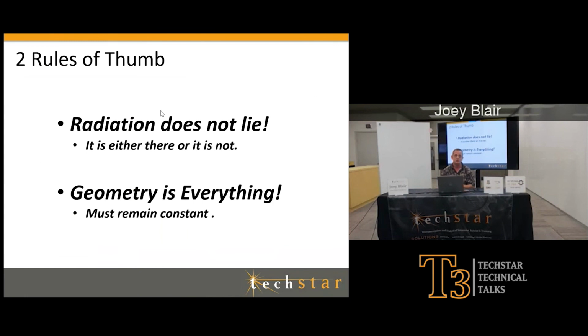Geometry is everything, which means if geometry is wrong, so is your measurement. If I'm trying to make a measurement here and I have my source pointed this way across, and I installed my detector way up here, and I'm suddenly coming out saying, hey, this thing never goes to 100%. Well, actually, what will happen is it's going to go to 100% early, because it's going to start filling, and it's just going to run out of space. I'm not going to measure this top portion. Well, it's because I've installed my detector too high. It needs to come down, or these things need to match up. So geometry is important, making sure our angles are important, and just remember those 2 things.